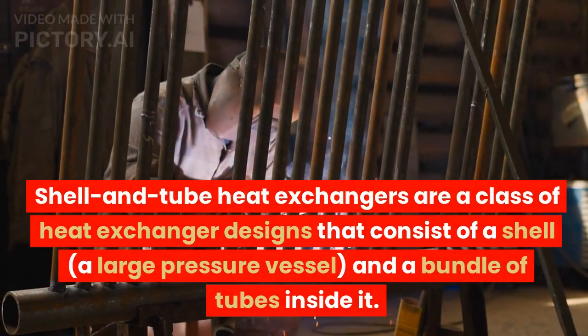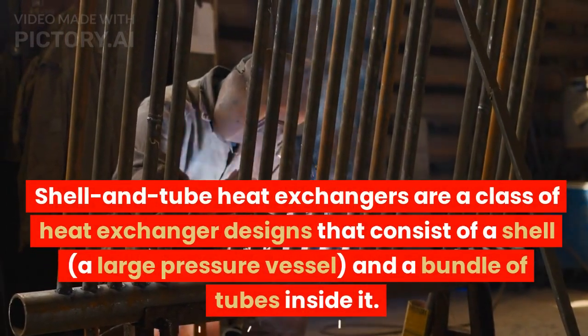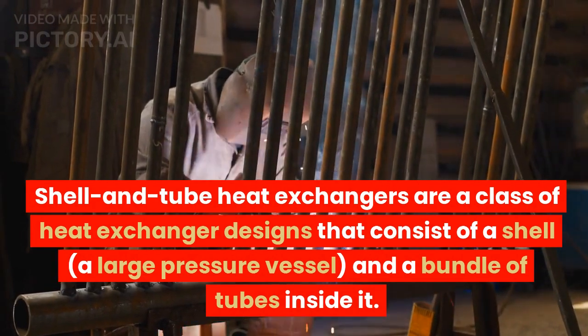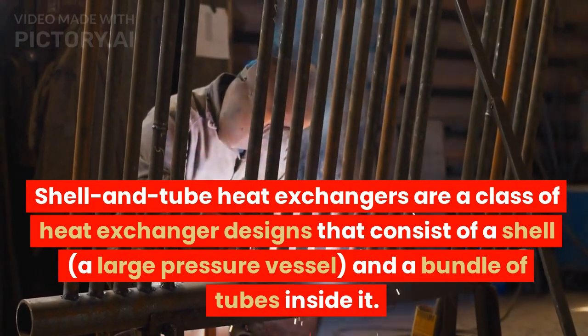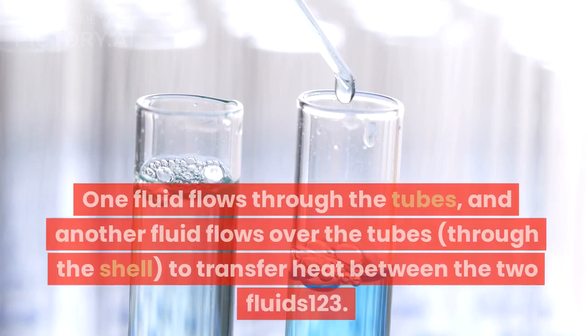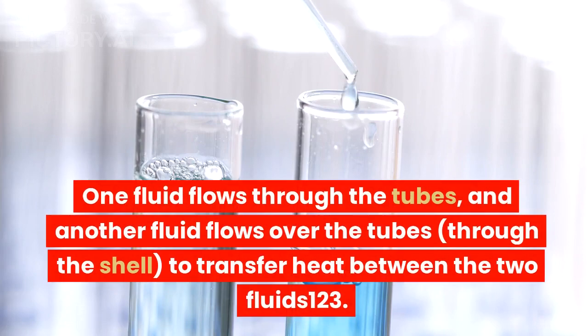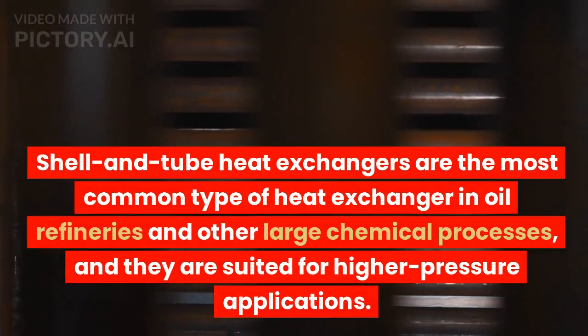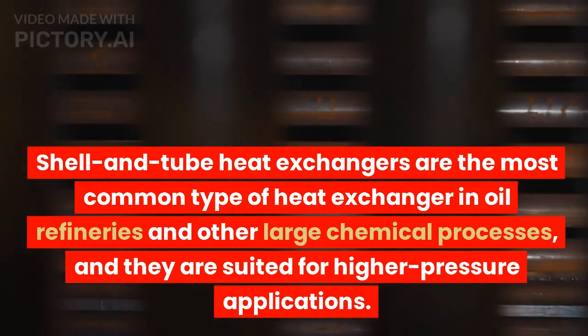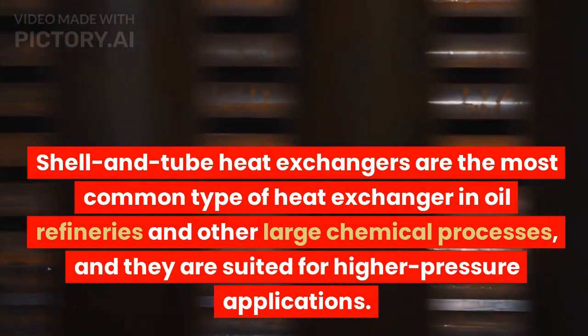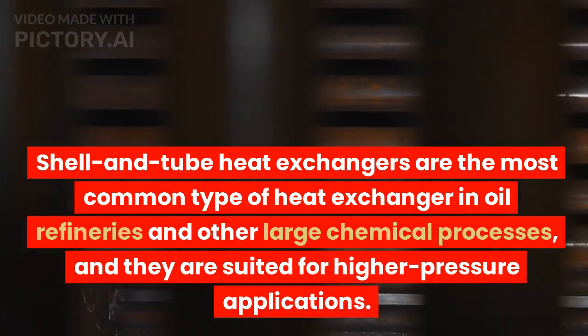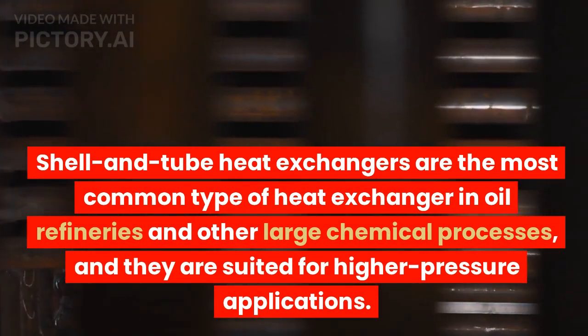Shell and tube heat exchangers are a class of heat exchanger designs that consist of a shell, a large pressure vessel, and a bundle of tubes inside it. One fluid flows through the tubes, and another fluid flows over the tubes, through the shell, to transfer heat between the two fluids. Shell and tube heat exchangers are the most common type of heat exchanger in oil refineries and other large chemical processes, and they are suited for higher pressure applications.